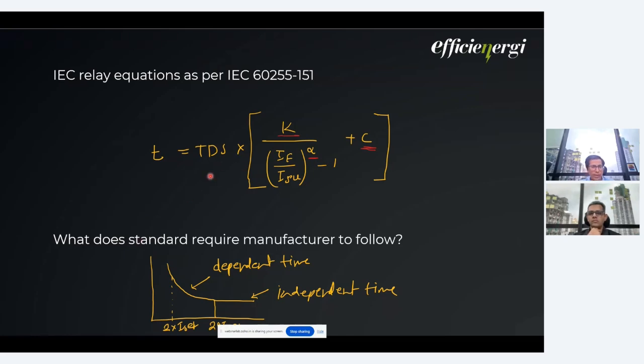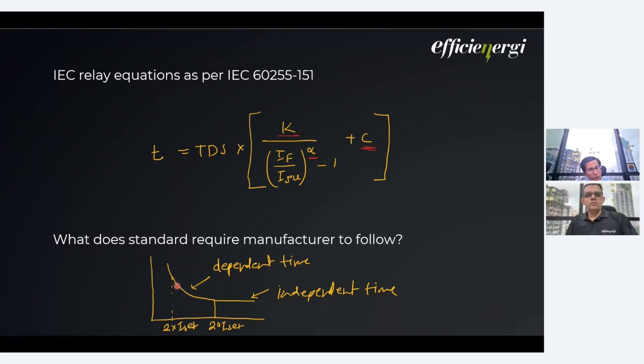This equation is given by IEC, and what IEC requires is that the dependent time characteristics should comply in the range from 2 times the set value up to 20 times the set value. In some relays you must have seen that after 20 there is a definite time characteristic, and then it doesn't follow any equation. That is not a limitation of the relay. It is basically a requirement of the standards, and every manufacturer tries to follow these requirements.